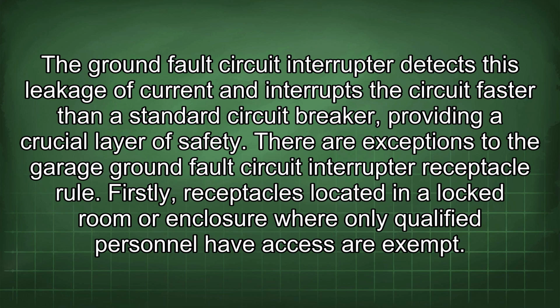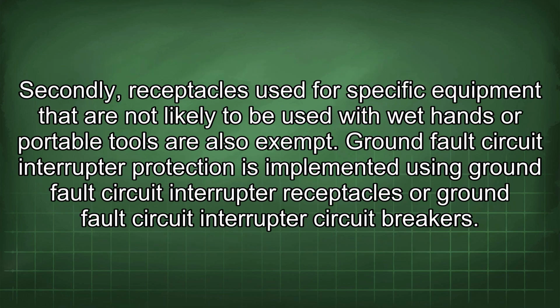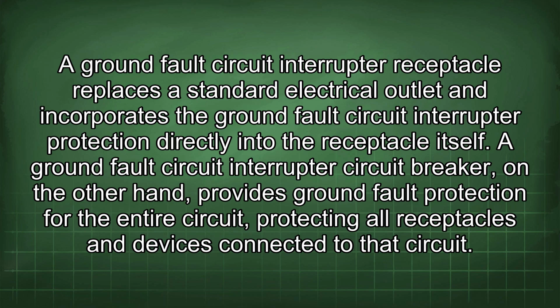There are exceptions to the garage ground fault circuit interrupter receptacle rule. Firstly, receptacles located in a locked room or enclosure where only qualified personnel have access are exempt. Secondly, receptacles used for specific equipment that are not likely to be used with wet hands or portable tools are also exempt. Ground fault circuit interrupter protection is implemented using ground fault circuit interrupter receptacles or ground fault circuit interrupter circuit breakers. A ground fault circuit interrupter receptacle replaces the standard electrical outlet and incorporates the ground fault circuit interrupter protection directly into the receptacle itself.